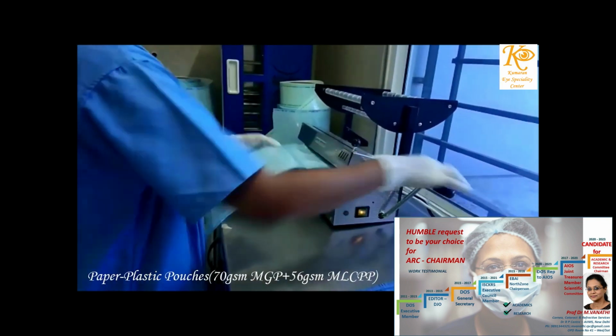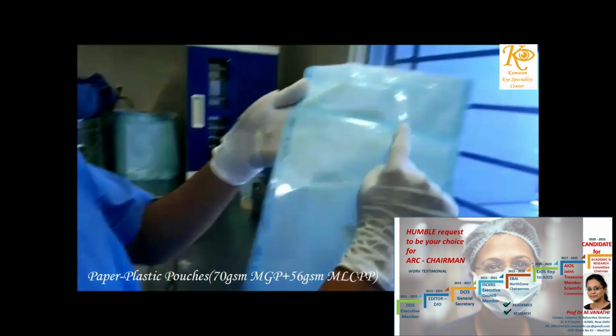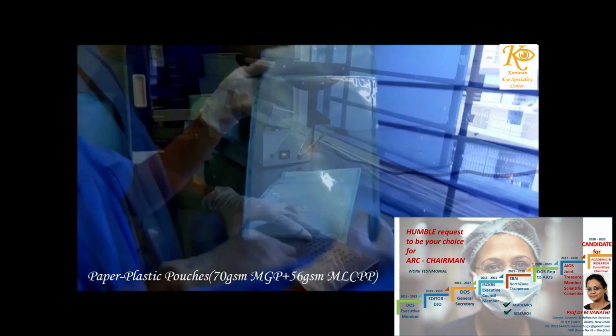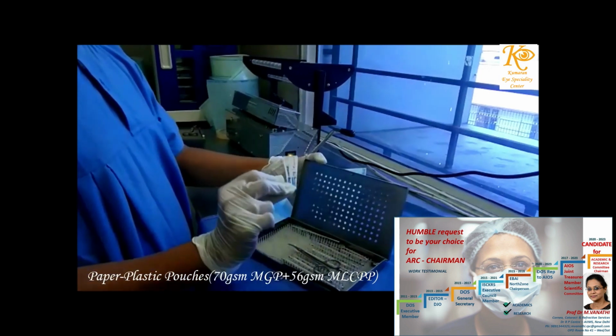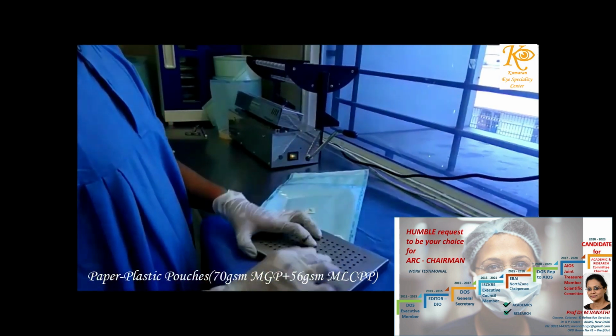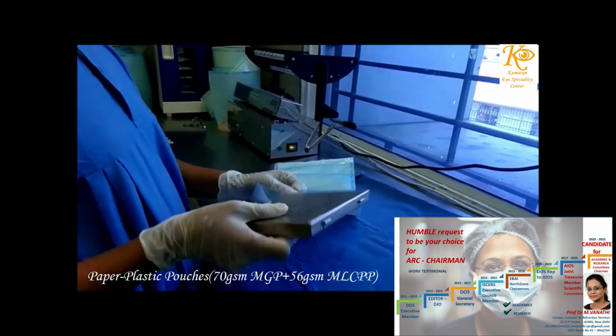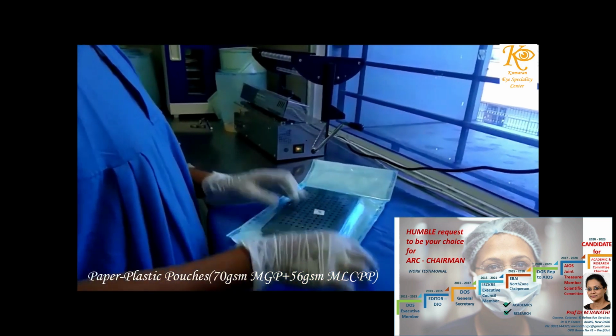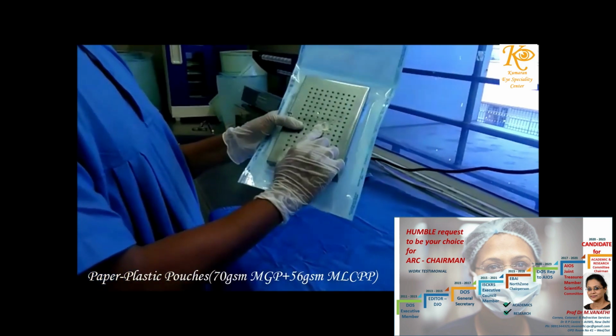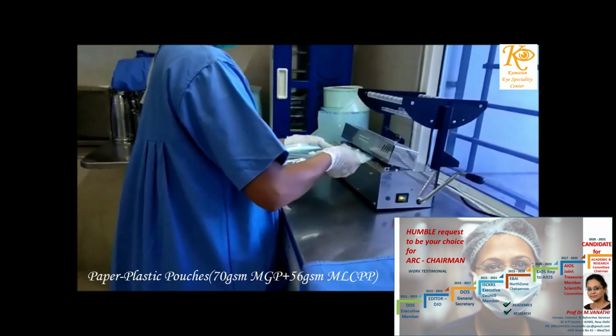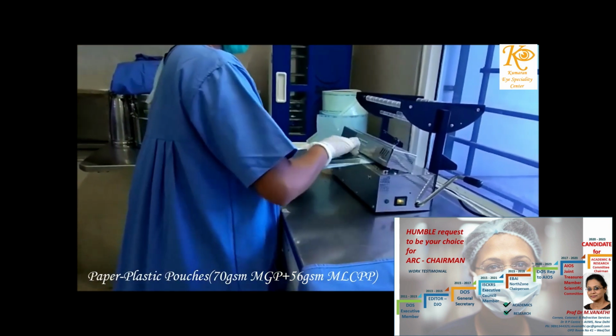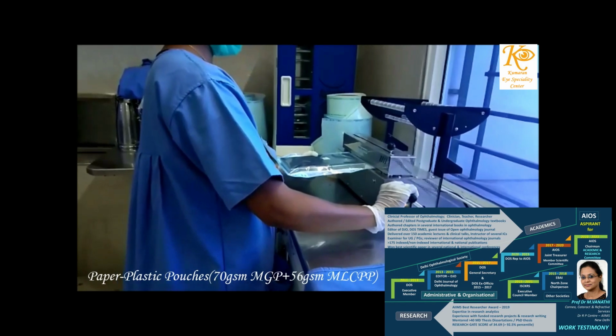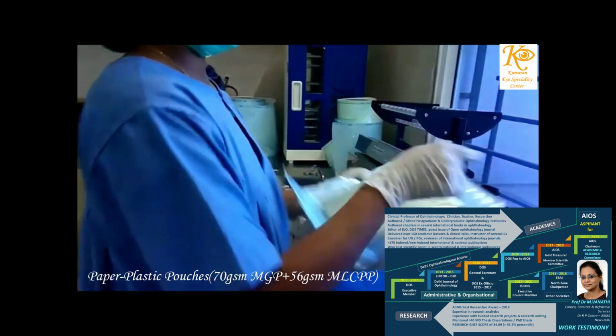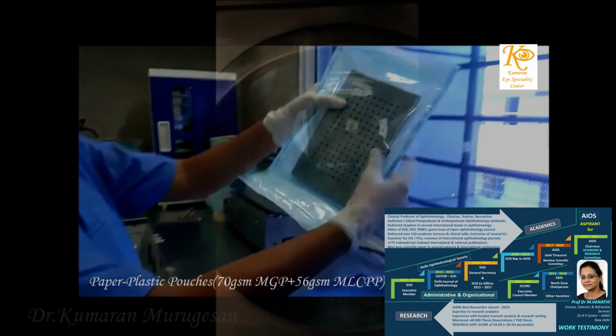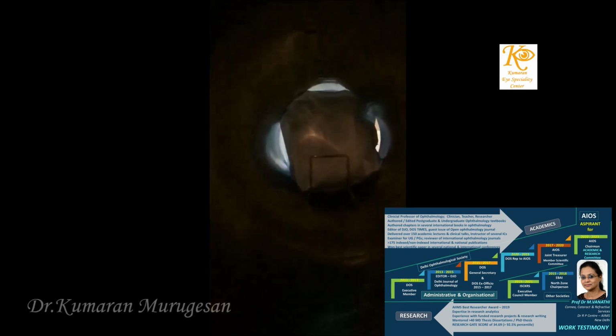Plastic paper pouches made up of medical grade paper and multi-layered cast polypropylene can also be used. Instruments can be placed unwrapped only in an immediate use steam sterilizer, otherwise known as flash sterilization, and these instruments should be used immediately. This form of sterilization is used only for instruments that become unsterile during surgery or to sterilize instruments in between the surgical procedure. Immediate use steam sterilization should not be used as a regular method to sterilize surgical instruments.